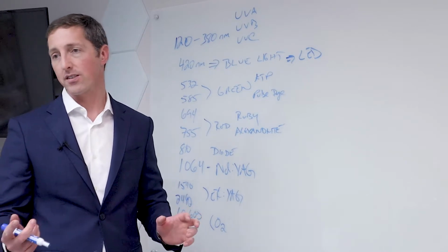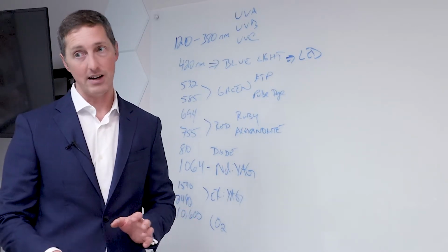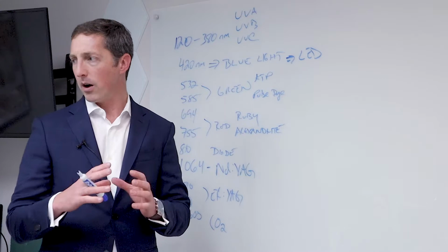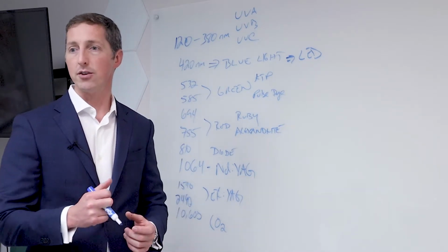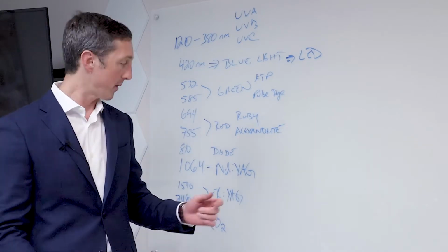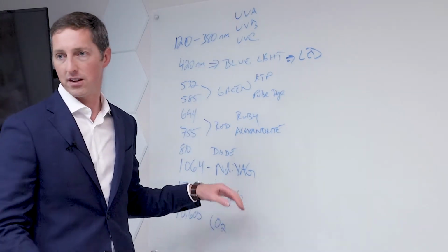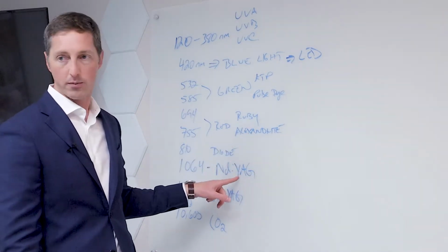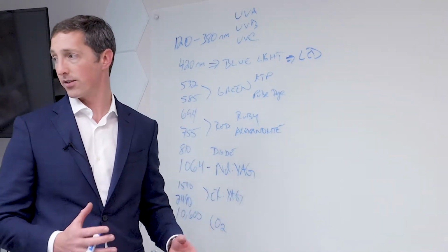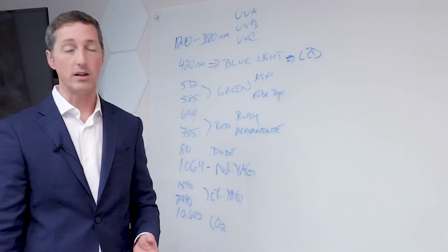It just so happens that darker skin types also have very, very dark hair. And as a consequence, they have a lot of melanin volumetrically within a hair follicle that still allows us to achieve effective absorption, despite the fact that the absorption coefficient is rather low. It's been said that the Alex has 3 times the absorption of melanin than the YAG. So that just goes to show just how much more effectively absorbed it really is.